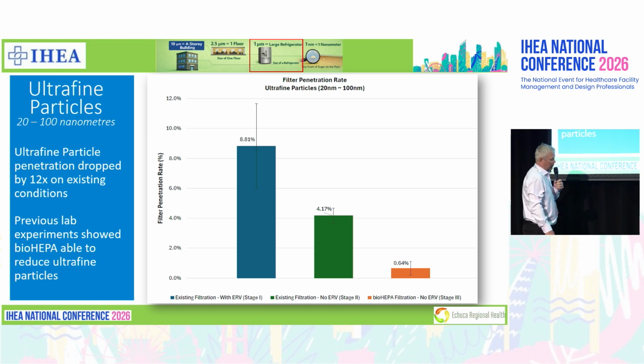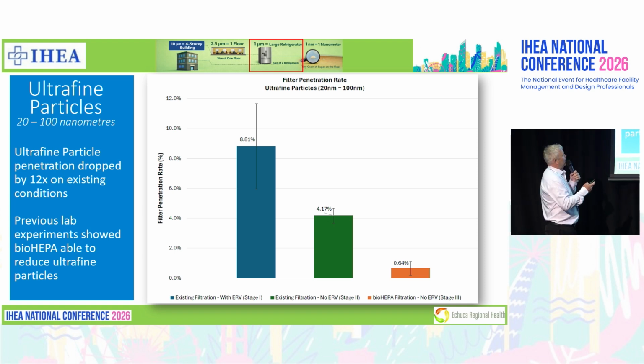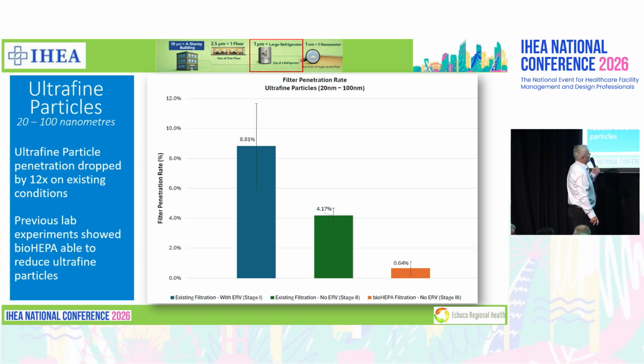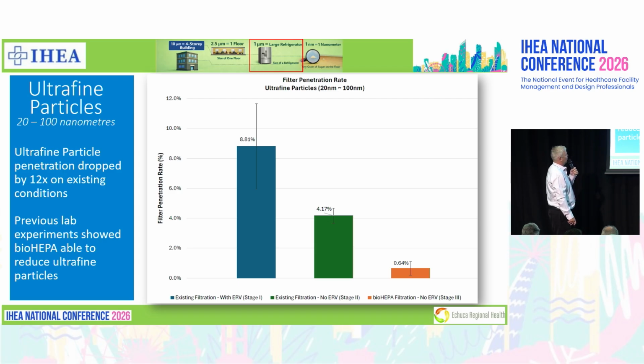Now if you look at the ultra-fine stuff, which is we're now starting to get down into our Coke cans and our grains of sugar, our filter penetration rate on our intervention unit is at 0.64%, and our penetration rate of our existing system, without doing anything, is only 8%, which is still pretty damn good without doing anything. But you can see in terms of metrics that's about a 12 times reduction on what we were putting into our space.